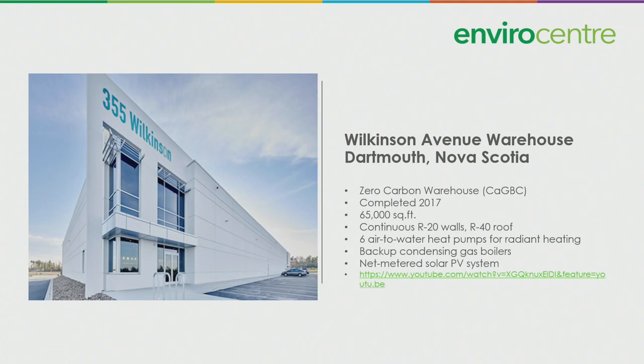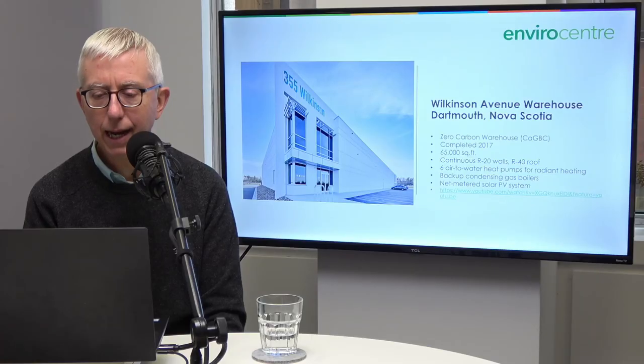And here's one that we also have a video of that we'll show you at the end, but it's the Wilkinson Avenue Warehouse in Dartmouth, Nova Scotia. And I include this because it actually represents a scenario that could be applied in a retrofit situation to warehouses, for example. It's a 65,000 square foot warehouse, and which they insulated with R20 walls and an R40 roof. They also were able to upgrade the slab, which might not be as feasible for an existing structure, but they only use 6 air-to-water heat pumps for radiant heating of this building. It does have backup condensing gas boilers, but it is a zero-carbon warehouse nevertheless. They have a net-metered solar PV system on the roof as well. And I have a video here for you to watch.